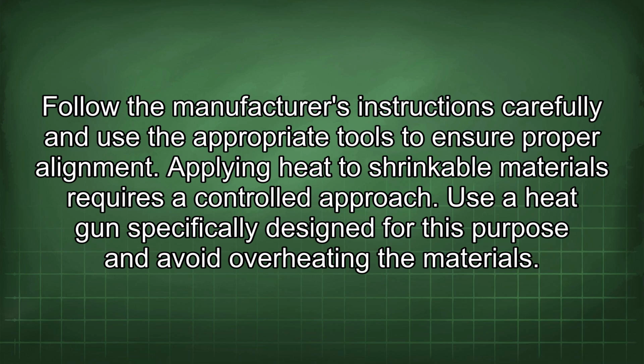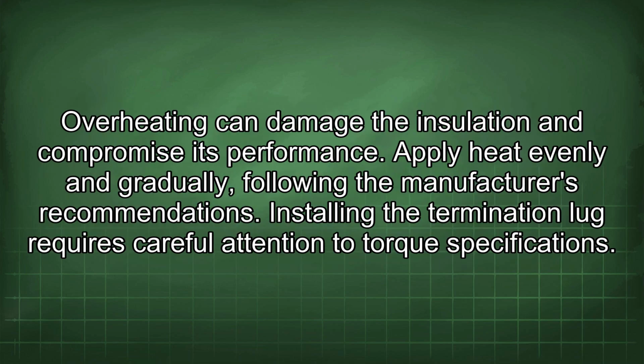Applying heat to shrinkable materials requires a controlled approach. Use a heat gun specifically designed for this purpose and avoid overheating the materials. Overheating can damage the insulation and compromise its performance. Apply heat evenly and gradually, following the manufacturer's recommendations.